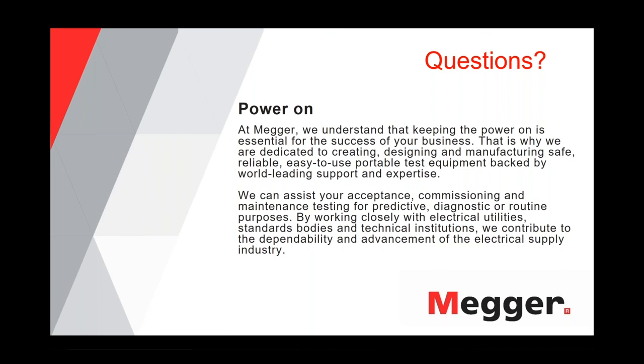If you do a VLF test with the right test parameters, then you will have no problems with water tree induced aging or failures for 2 to 3 years when you pass the test. Because if you had a critical sized water tree, as Javier showed in the presentation, a properly conducted VLF test will rake these imminent failures out of your system. So for the VLF test, you say 3 years, for instance, some people do 5 years, that also depends.